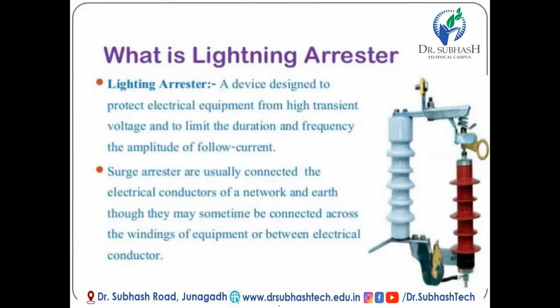Surge arrestors are usually connected between the electrical conductors of a network and earth, though they may sometimes be connected across the windings of equipment or between electrical conductors. Here is the image of a lightning arrestor. The lower end is connected to the earth and this end is connected to the electrical equipment.